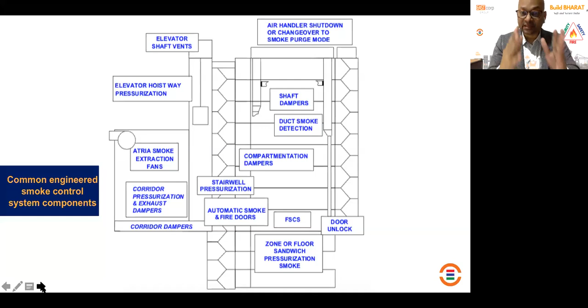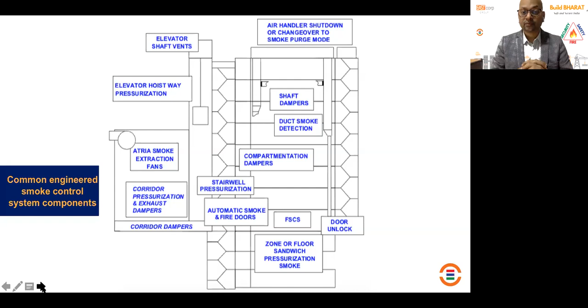If you look at it, it is a little complex to understand, but you can always simplify the system by way of engineering. If you have one fire and life safety expert or one coordinator who is going to understand the smoke well coming in from HVAC, coming in from the electrical perspective, then you can have all integration possible. Let's look at it in reality, how this is going to work. Now, dampers, which are basically placed on AHUs, their job is opening and closing. Now, when to open, when to close, who will decide? The fire alarm system will decide. So essentially, we are talking about integration between the fire alarm and the HVAC system. And what is the catalyst in between? Your dampers.